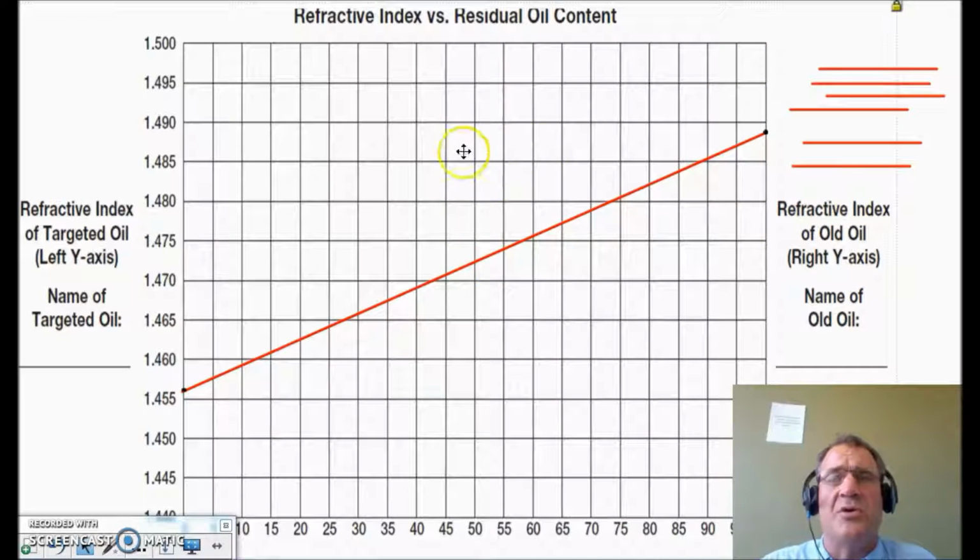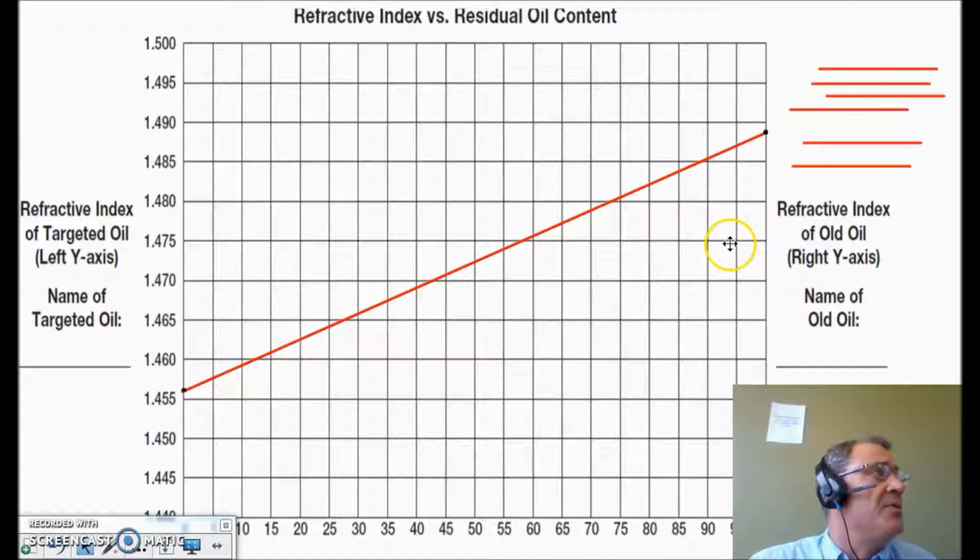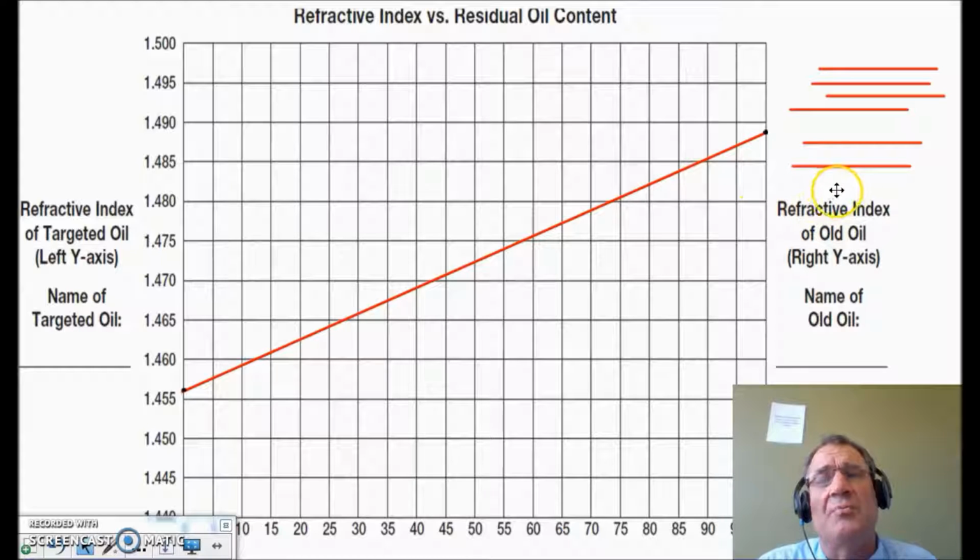So the next thing we're going to do is change the oil in the system. We're going to do the first oil change. This usually takes about 3 oil changes. So we're going to pump the system down and change the oil in the compressor. We're going to remove the original alkylbenzene oil as much as possible, and replace what we can get out of the compressor with polyolester. And then we're going to run the system for 24 hours. Then we're going to come back and take a sample of the oil that's in that system and see what the refractive index is.